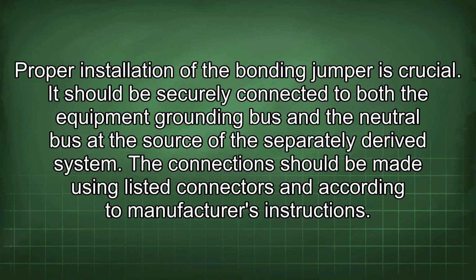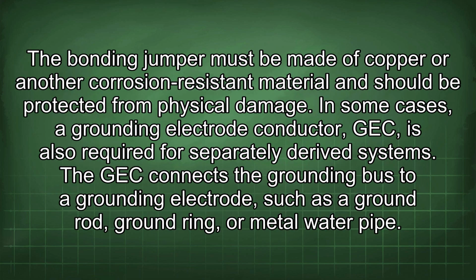Proper installation of the bonding jumper is crucial. It should be securely connected to both the equipment grounding bus and the neutral bus at the source of the separately derived system. The connection should be made using listed connectors and according to manufacturer's instructions. The bonding jumper must be made of copper or another corrosion-resistant material and should be protected from physical damage.